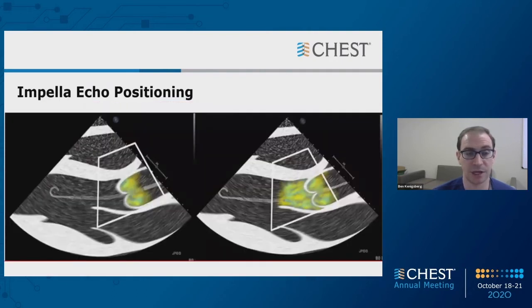This is a representative graphic of how color flow Doppler can help us. What you'll do is put your color flow Doppler box across the aortic valve and across the aorta, and you're looking for the echo artifact created by this motor unit. The artifact should always be completely above the aortic valve, as shown here on the left, since the motor housing is superior to the outlet port. On the right, we see the echo artifact below the aortic valve, suggesting an Impella positioning too far into the ventricle.